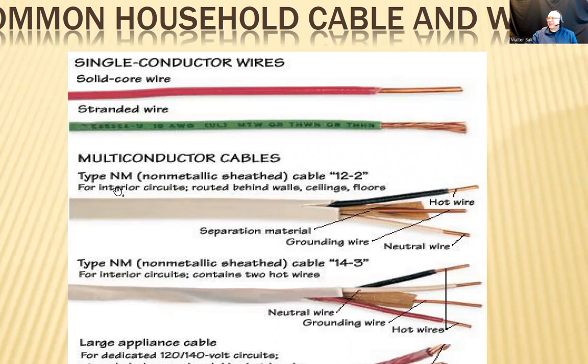So here's the jacketing type of NM, non-metallic. That means that the jacketing is non-metallic and it's supposed to be installed in a non-metallic environment. So when you go to a framing, you would install that on a wooden framing or anything that's non-metallic. But if you have metal studs or metal framing, you're not supposed to use that cable directly, in a way that it touches the metal framing directly. Sometimes, if somebody really wants to do that, they would put a little 2x4. They would mount it to the steel frame, and then they would mount the cable to the wooden 2x4.